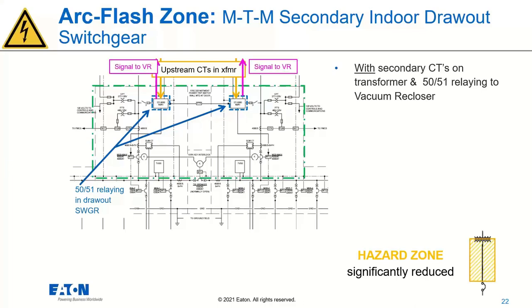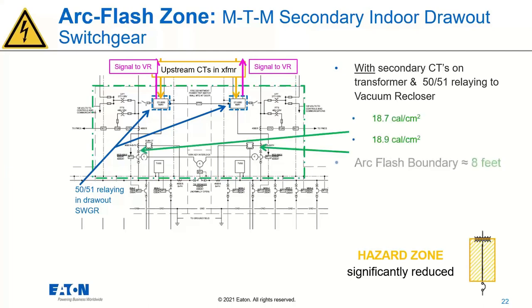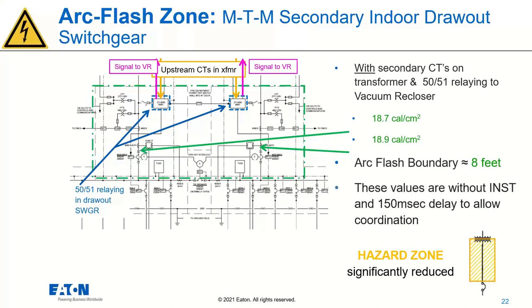So signaling that vacuum recloser with this 50/51 rather than allowing it to wait on its own, we're going to see a huge reduction in the overall arc flash energy, down now below the permissible level of 40 cals, even below the 20 cal limit. And again, this is an always on scenario. We could even further reduce this by activating a maintenance mode on the 50/51 relay.